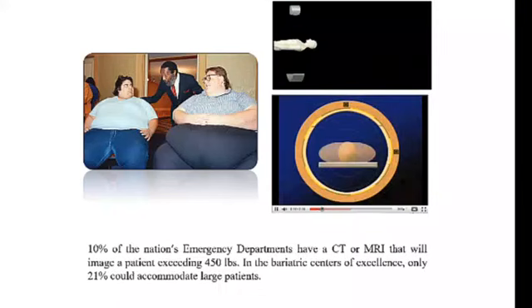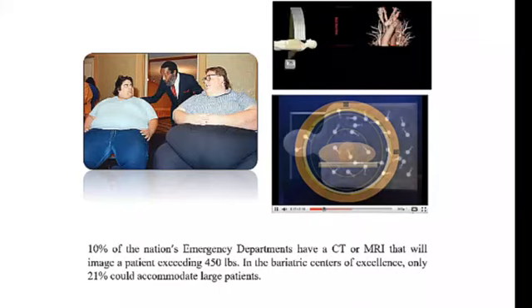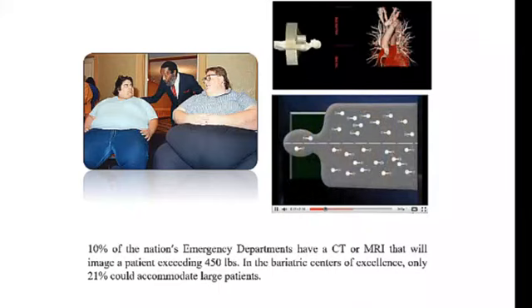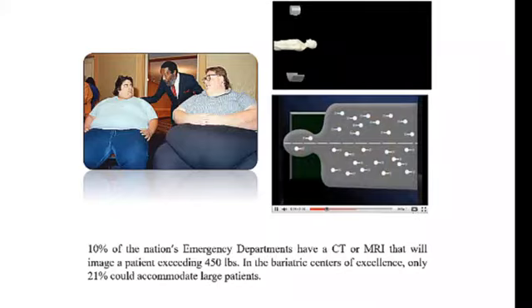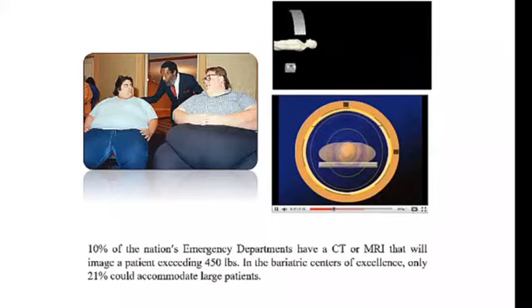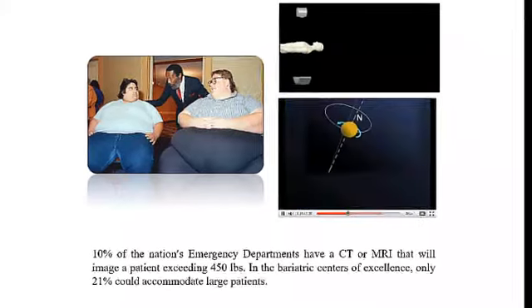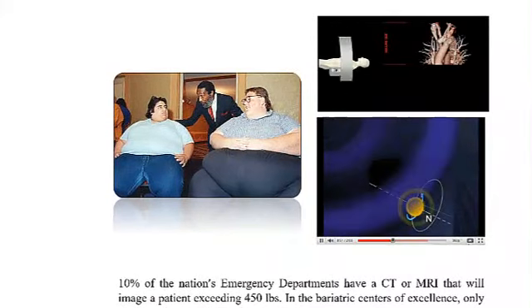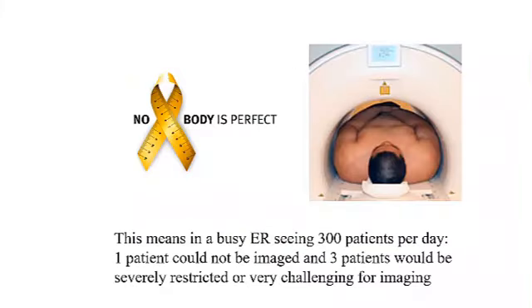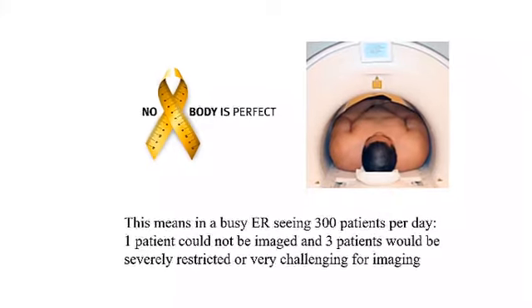10% of the nation's emergency departments have a CT or MRI that will image a patient exceeding 450 pounds. In the bariatric centers of excellence, only 21% could accommodate the largest patients. This means in a busy ER, which sees about 300 patients per day, one of those patients would be so big they could not be imaged, and 3 patients would be severely restricted or very challenging for imaging.